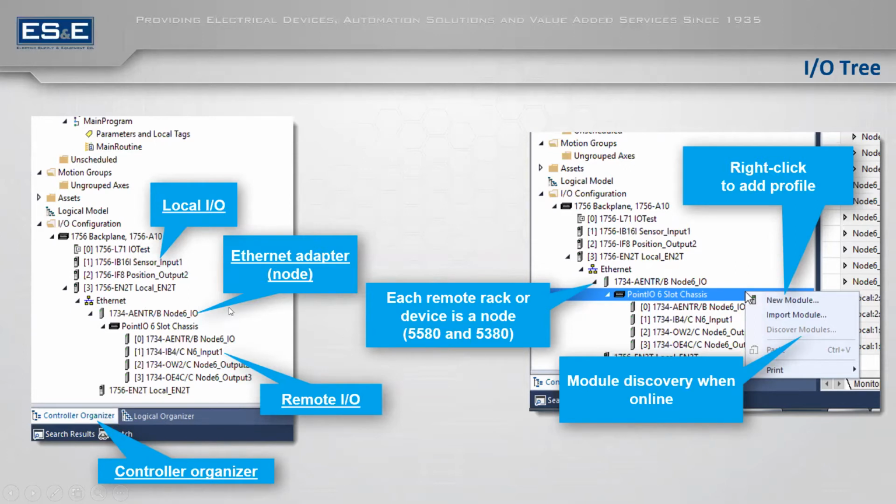The other thing is you can add remote I/O, for which you will add an Ethernet adapter of some sort to communicate back and transfer I/O. Remote I/O, even though it is under your Ethernet settings, uses what they call class 1 communications, which is different than, say, messaging or a PanelView or an OPC. All those communication types are class 3 communications.